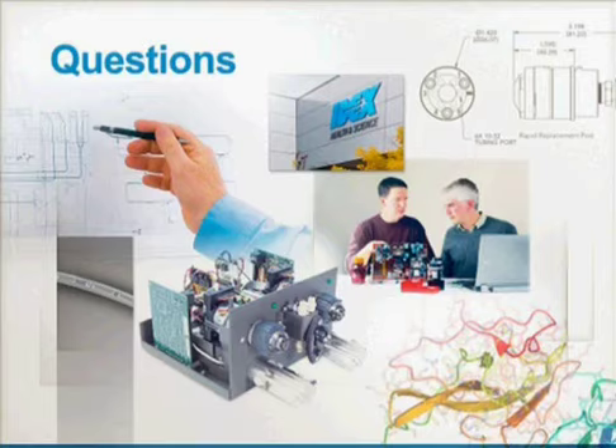All right, next question. How does the complexity of integrating a syringe pump compare with a piston pump? This is a good question. I'll start the fielding of this, and either of you can jump in with me. We talked quite a bit in the earlier program about the syringe pumps being really good at a number of things, and Dave basically talked about the fact that if you use the full stroke, they're quite good at what they do. But if you're doing the kind of gradient work that we've discussed, and you want to use part of the volume of the pump, for instance, and you want to control that flow very precisely, there are some advantages to a piston pump with especially some feedback control, which we've talked about.